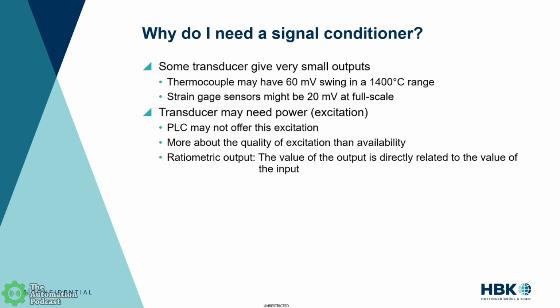You've got a 1400 degrees Celsius range, and you might have a 60 millivolt swing. That's a pretty small resolution there. As I mentioned, strain gauge sensors. If you have a full bridge load cell, something like that, under the best case scenario, you might have a 20 millivolt output at full scale. 20 millivolts is a very small voltage to be measuring with maybe a plus or minus 10 volt input on your PLC, right? You're talking about a very small percentage of that measurement range.